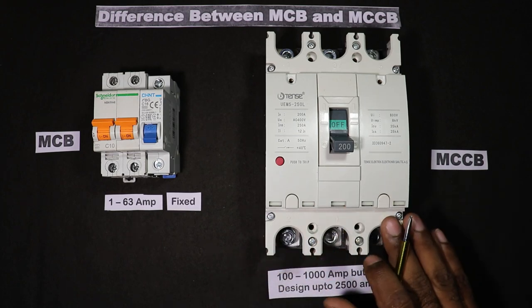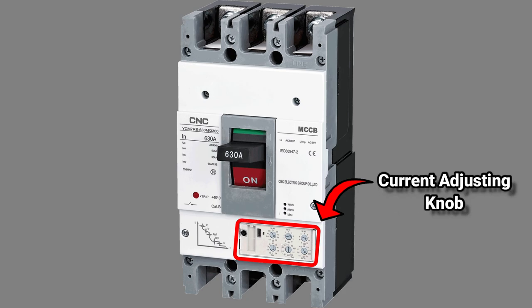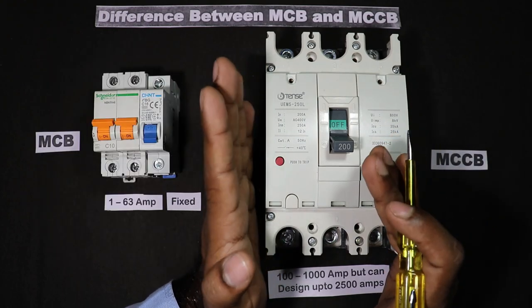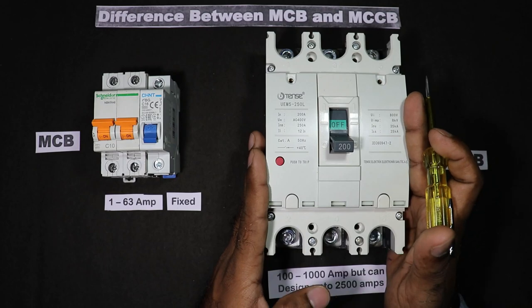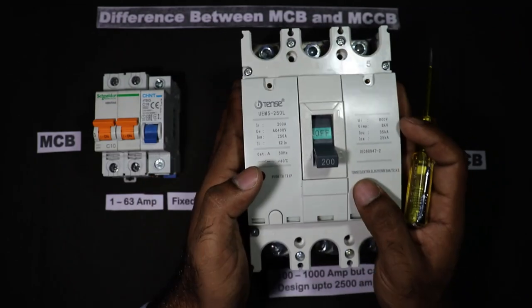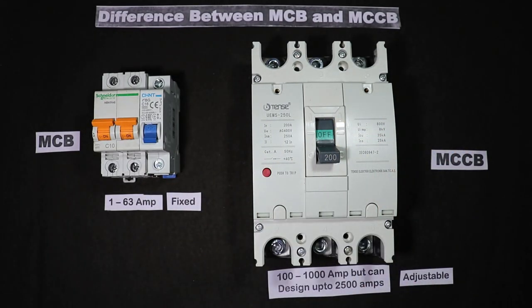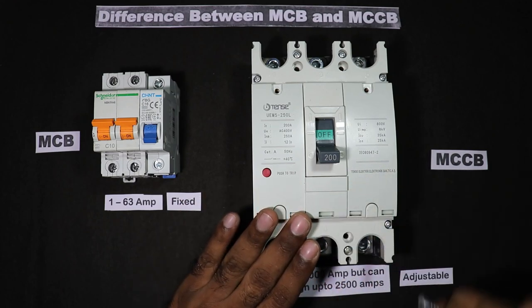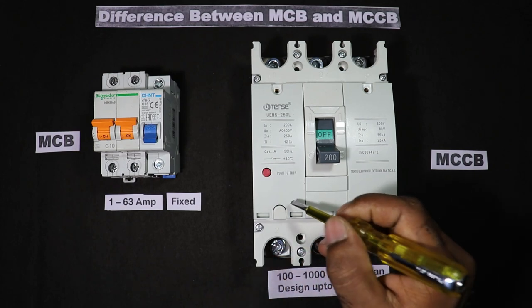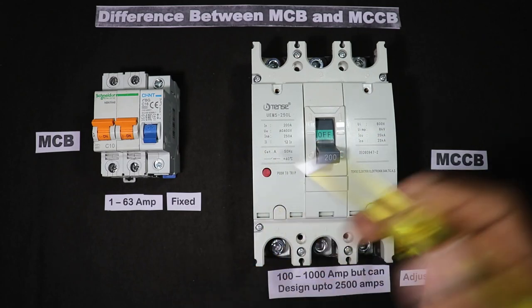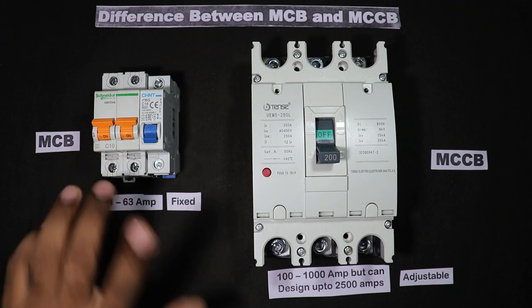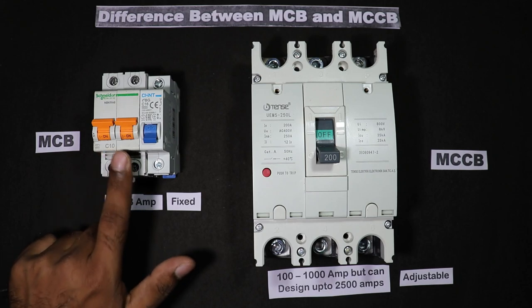Friends, the current rating of MCCB can be adjusted. There is a knob on the MCCB — in many MCCBs you will find a knob, and by rotating that knob the current rating can be decreased. The MCCB I have right now is of 200 ampere, as written here. Suppose the current rating at the installation place is 180 ampere — in that condition you can rotate the knob to decrease the current rating of the MCCB. The rated current cannot be further increased, only decreased. But in MCB you won't find any knob to increase or decrease the current rating.